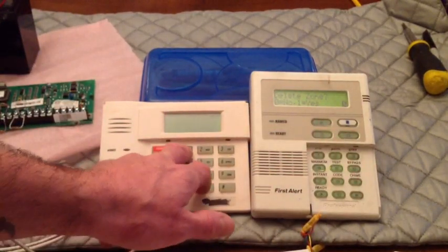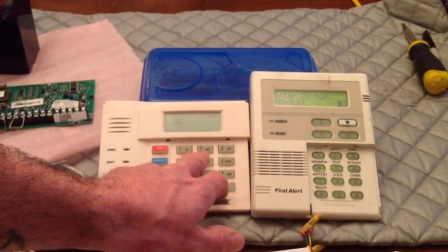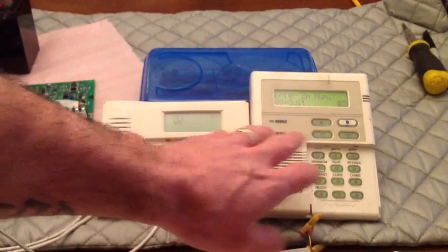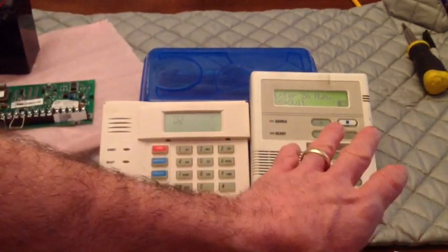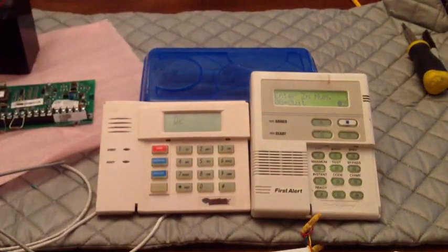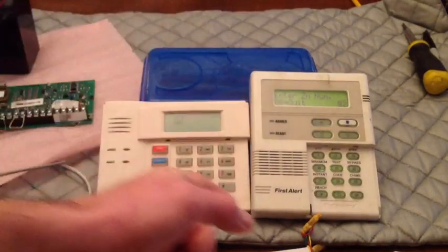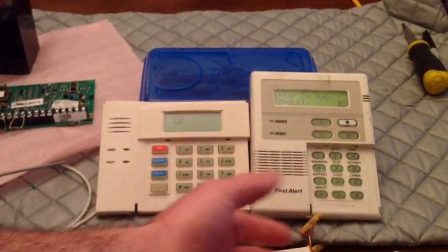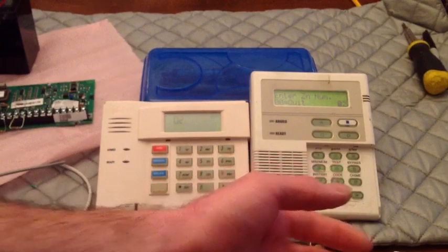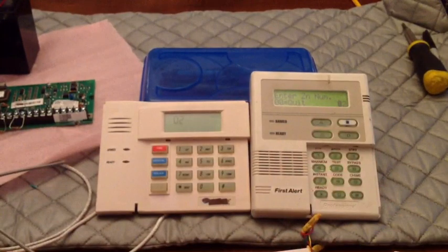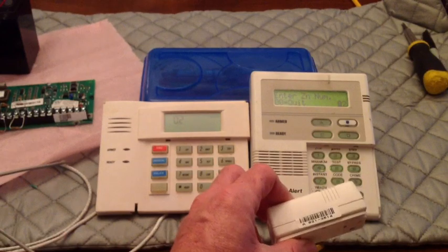If I wanted to delete it totally, you would hit 1 at this field. And it's going to delete that zone and wipe out serial numbers, wipe out any information that you put in there. So you could reprogram that zone to a new transmitter or what have you. Let's just say you had one go bad. You go in there, delete the zone, and reprogram it. Reprogram your wireless zone.